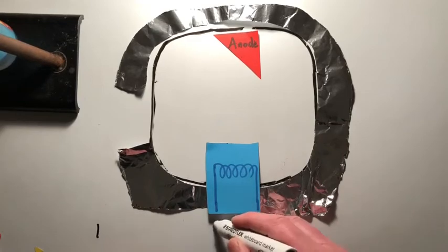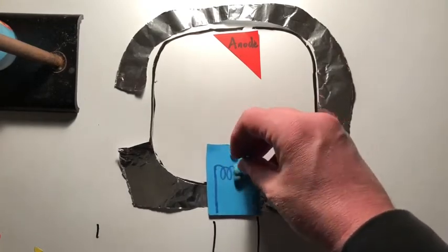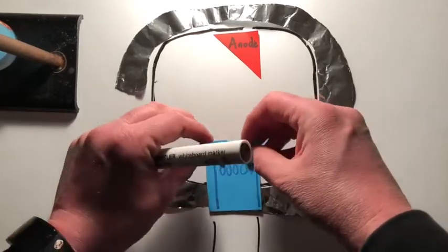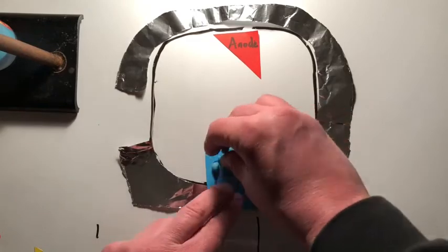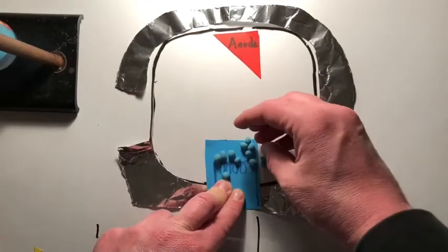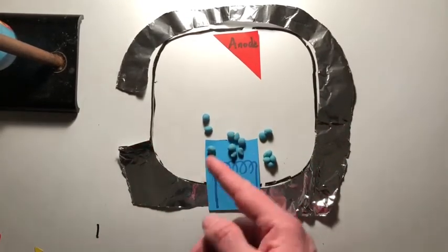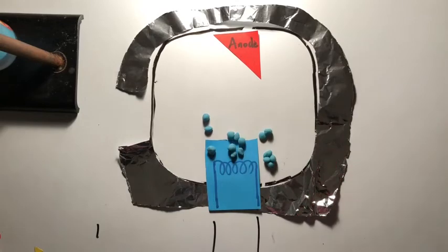Run a very modest voltage through this filament, and you're going to get some thermionic emission going on. Some of the electrons that are part of this filament are going to be given just enough thermal energy to escape from the force of attraction holding them onto the coil, and they're going to be emitted. Now, left to their own devices, they're just going to go around in all directions. We don't want that. We want them to target this anode.